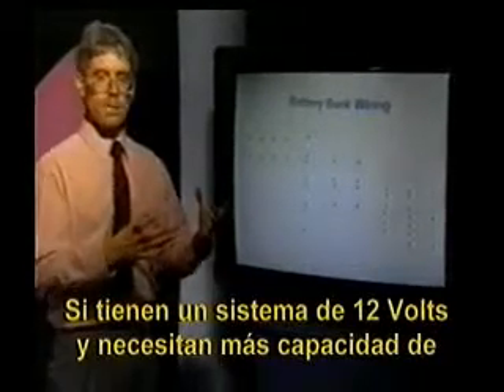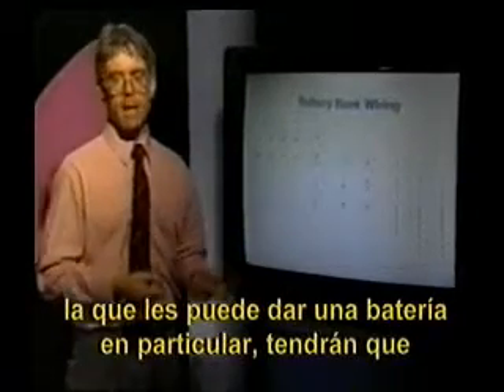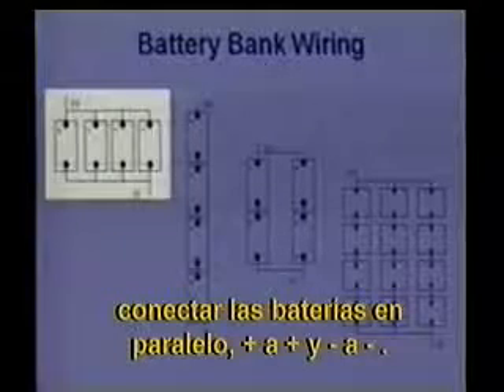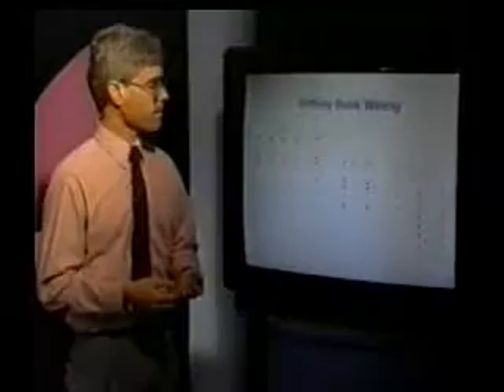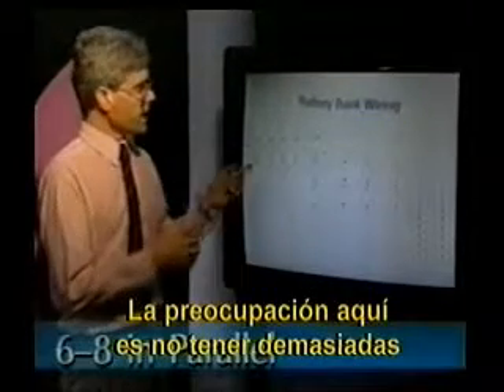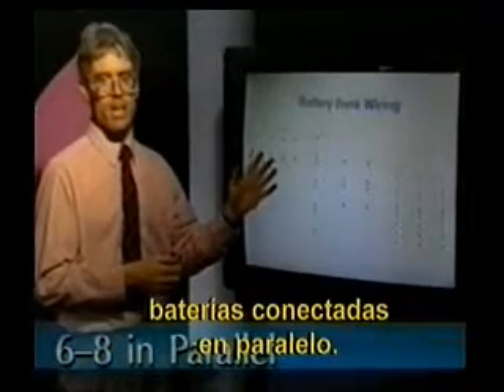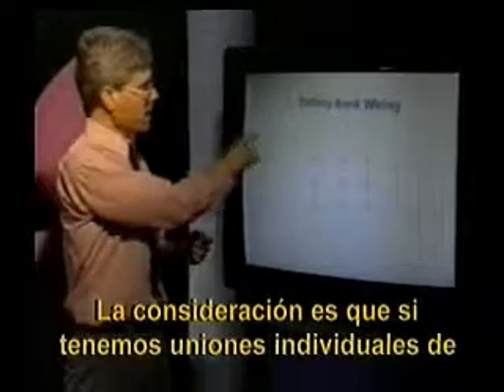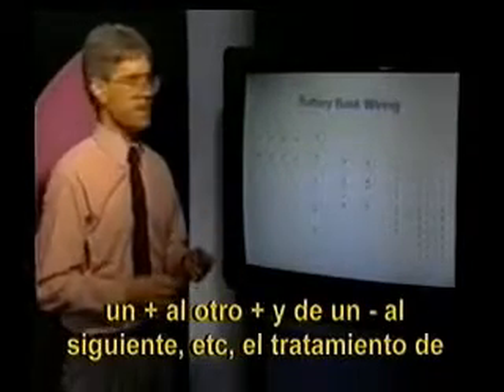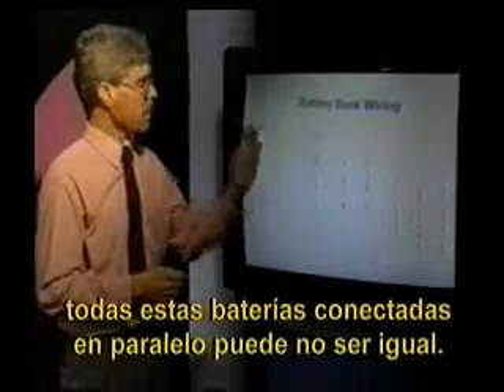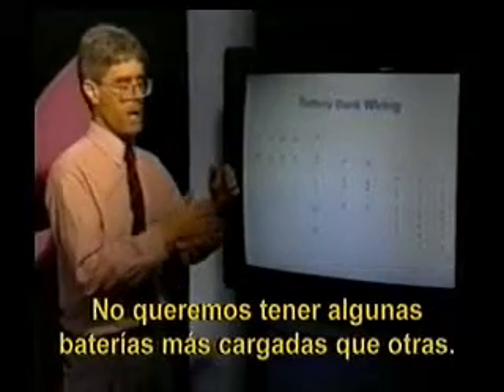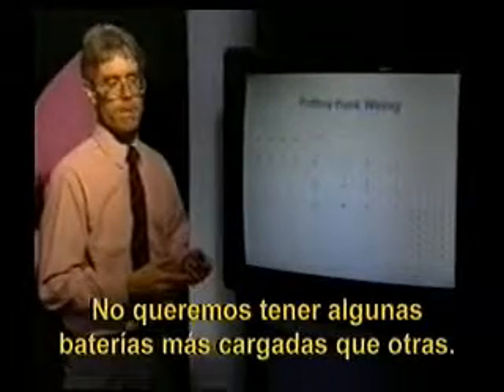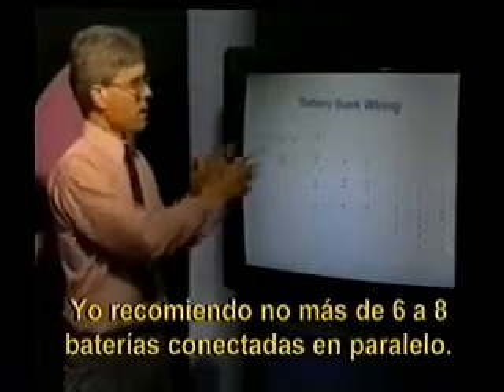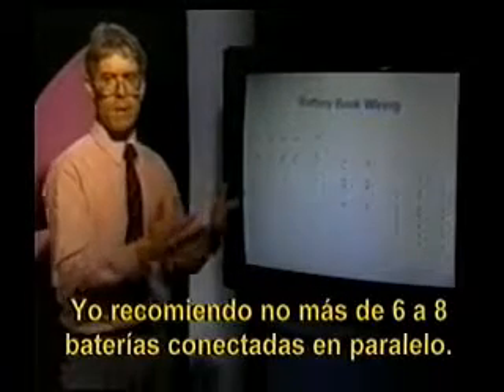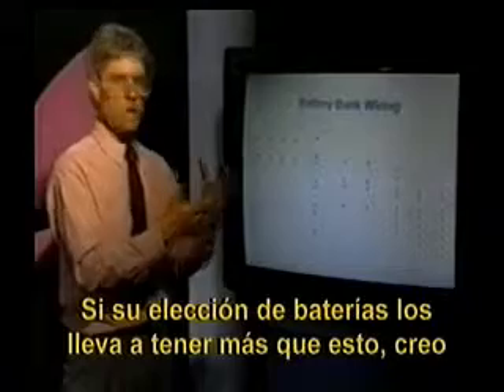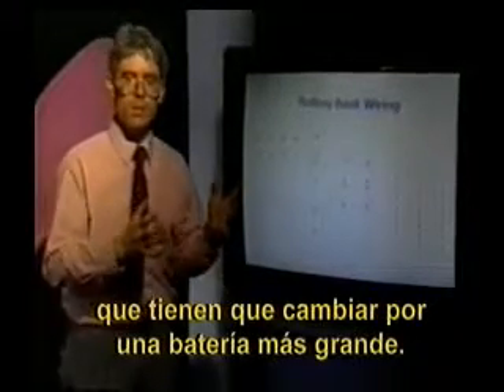If you've got a 12-volt system and you need to have more capacity than one particular battery can give you, you're going to wire your batteries in parallel, plus to plus and minus to minus. The concern here is not to have too many batteries wired in parallel. The consideration is that if we have individual linkages from one plus to the next plus and one minus to the next and so on, the treatment of all of these batteries wired in parallel might not be equal. You don't want to have some batteries being more charged than others, and so on. The guideline that I like to stick to is having no more than roughly 6 to 8 parallel batteries wired up. If your choices of batteries lead you to having more than 6 to 8 batteries in parallel, I think you should carefully look at choosing a larger battery.